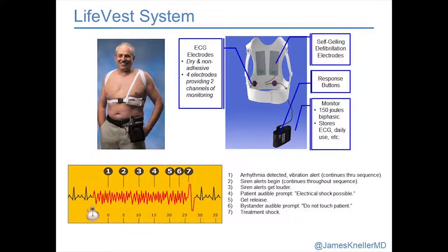So then you say, well, if the device can really be outside of your rib cage and just under your skin, then why does it need to be under your skin at all? And in fact, it doesn't have to be under your skin. There's the LifeVest. And the LifeVest is a clever device, defibrillator system under the left pec and in the back, 2 sensing electrodes, and a portable generator, battery that you wear on your belt. That's the computer and the battery. And that's a perfect defibrillator system. You could wear that your whole life if you were so motivated. You have to take it off to clean it, things like that. So there's times when therapy protection would be interrupted, but it's wonderful ICD protection.